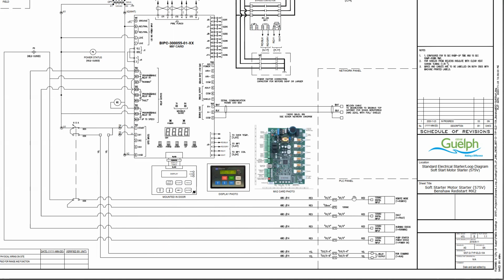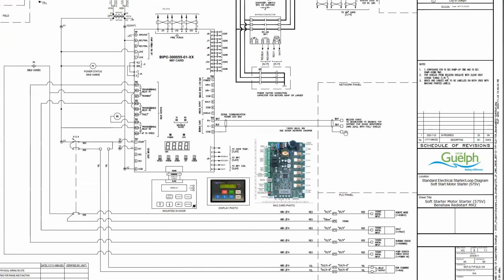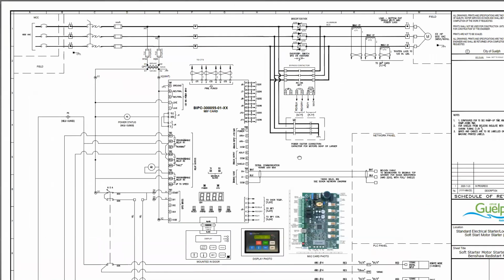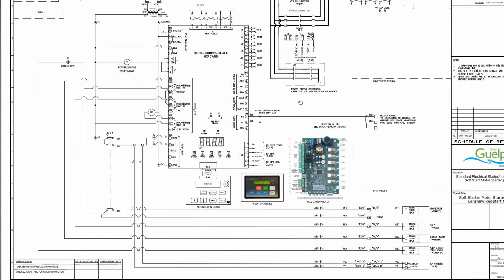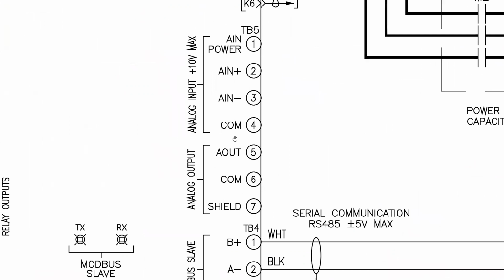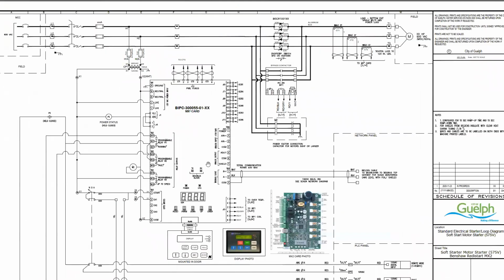Remote mode is the hand-off-auto switch here. In hand, we are not in remote. In auto, we are in remote. We've got our start input, DI here for the device. You can see there's our start input that comes up and starts the drive. And then our analog inputs are where? Analog inputs are here. Analog inputs and analog outputs for our drive. So this was taken out of the detailed control manual from Benshaw. Here's M2, the power factor correction capacitor for motors that are 50 horsepower or larger. So obviously this M2 is external to the drive and possibly optional.